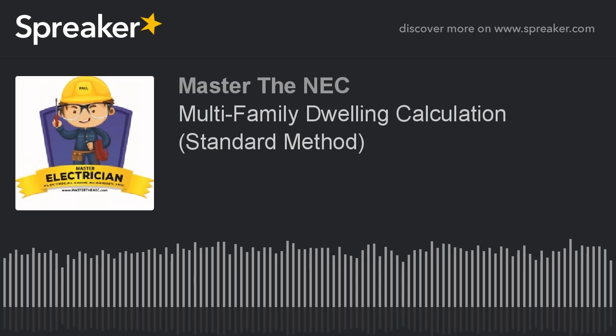So, we're allowed to apply a demand here to this value. And that demand is that 70% that we just talked about in 220.61(B). Since we had 489 amperes, we take the first 200 amperes at 100% because it says we can only apply this demand to that portion that's over 200. So, 200 is a given. So, we've got to write 200 down.